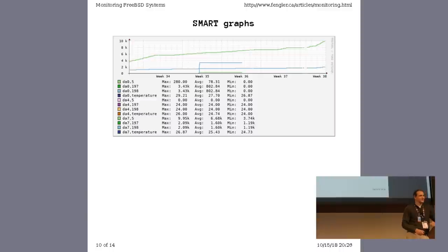How cold is that? Depends on the drive. The last time I was really aware of it, it kicked in at around 60 degrees Fahrenheit. What's that? Maybe 15, 16 Celsius? I think 15 Celsius is the number I've heard before for drives not liking the cold. Yeah. This does get into a very convoluted topic of the effect of temperature on air density and the Bernoulli effect, and we can talk about that for hours after my talk if you want.